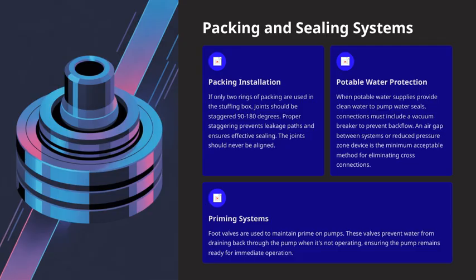Finally, let's talk about priming systems. Foot valves play a key role here. They're used to keep the pump primed. Essentially, they prevent water from draining back through the pump when it's not running, which means the pump is always ready to go when you need it. This small component makes a big difference in maintaining pump efficiency and readiness. All these systems, packing, sealing, potable water protection, and priming, are interconnected parts of ensuring reliable, safe, and efficient pump operation.